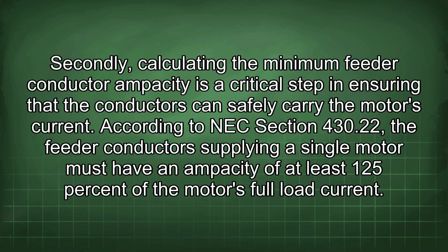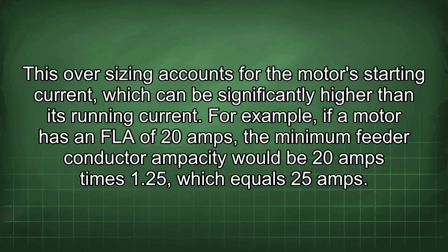the motor's current. According to NEC Section 430.22, the feeder conductors supplying a single motor must have an ampacity of at least 125% of the motor's full load current. This oversizing accounts for the motor's starting current, which can be significantly higher than its running current. For example, if a motor has an FLA of 20 amps, the minimum feeder conductor ampacity would be 20 amps times 1.25, which equals 25 amps.